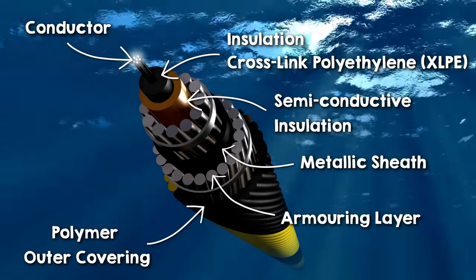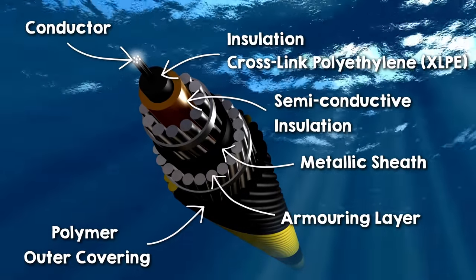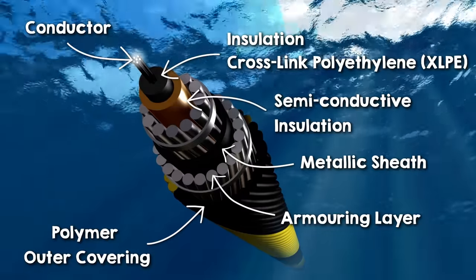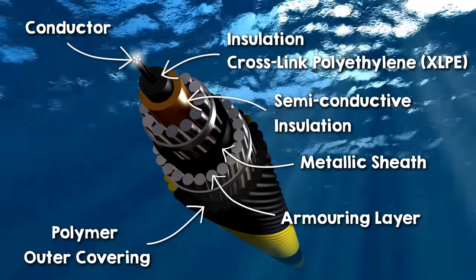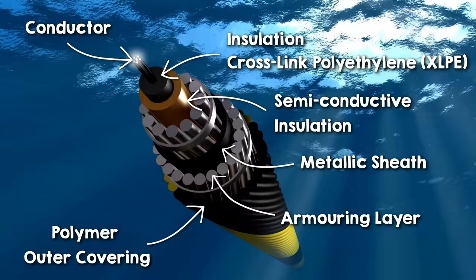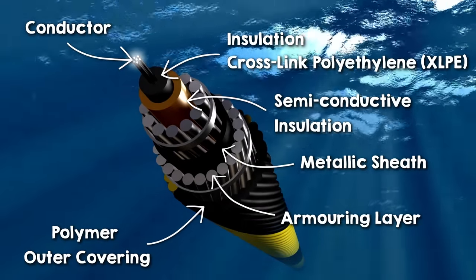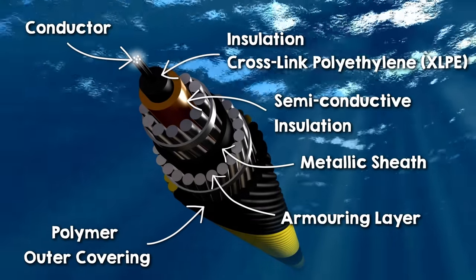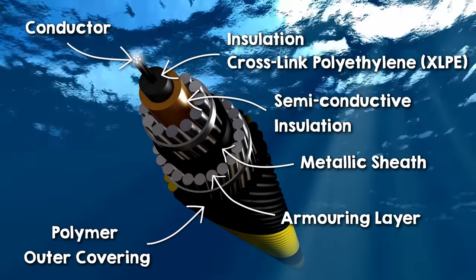Then there is a semiconductive insulation screen, a metallic sheath, an armoring layer, and lastly, an outer covering typically made of a polymeric material, which provides overall protection to the cable from the external environment and prevents corrosion. In some cases, fiber optic cable elements are included for communication and monitoring.